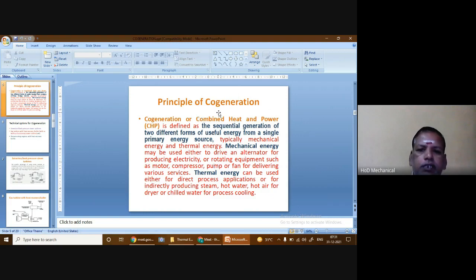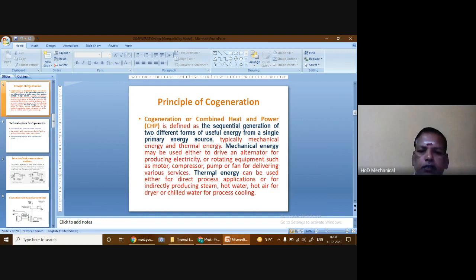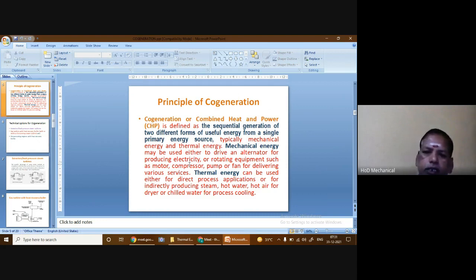The principle of cogeneration — cogeneration, or combined heat and power — is defined as the sequential generation of two different forms of useful energy from a single primary energy source, typically mechanical energy and thermal energy. Mechanical energy may be used to drive an alternator for producing electricity or rotating equipment such as motors, compressors, pumps, or fans. Thermal energy can be used for direct process applications or for indirectly producing steam, hot water, hot air for dryers, or chilled water for process cooling.